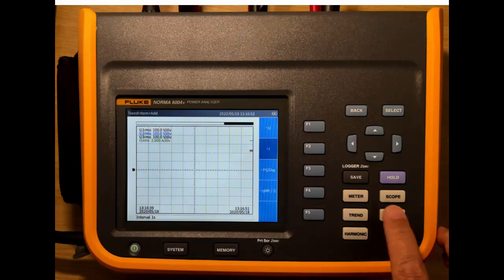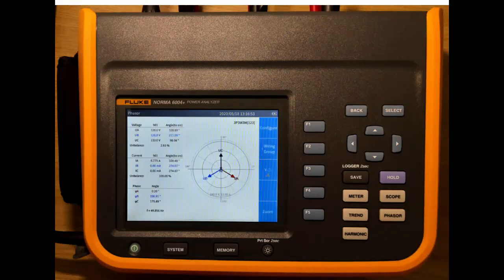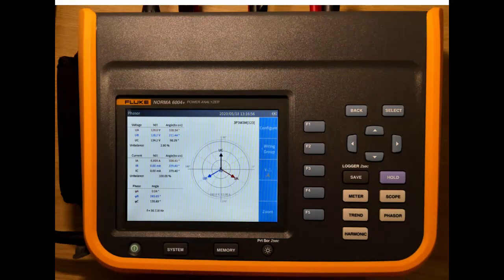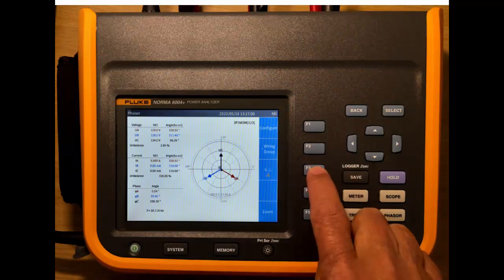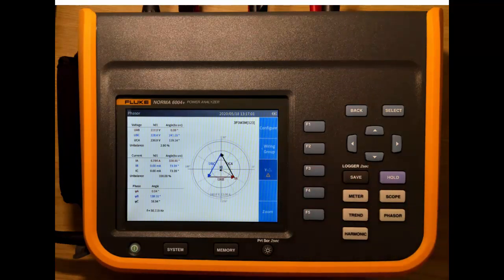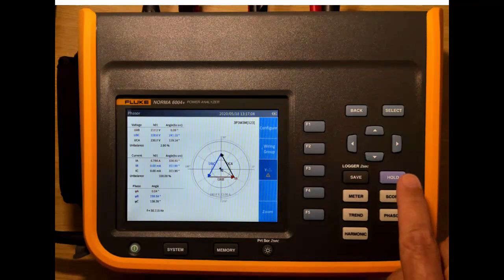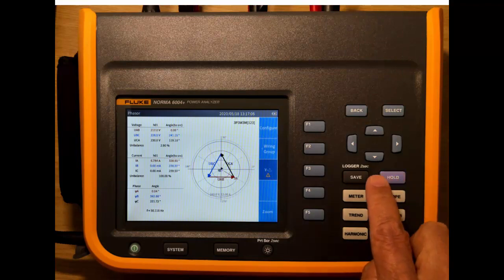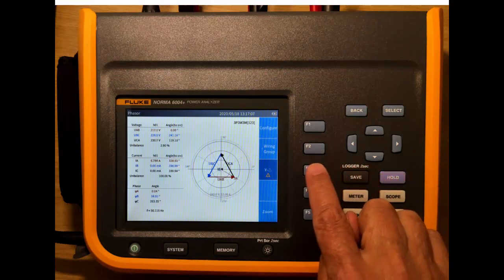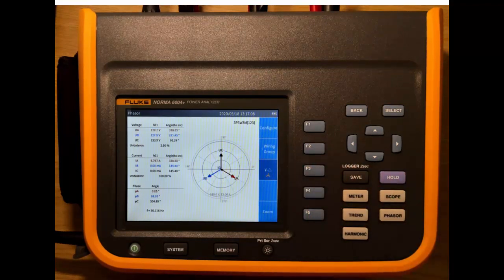Next we have the phasor diagram. This helps during the setup to make sure that we've connected the right way around. This one's showing Y currently. We can also show this as a delta phasor as well. And we can go back to Y again.